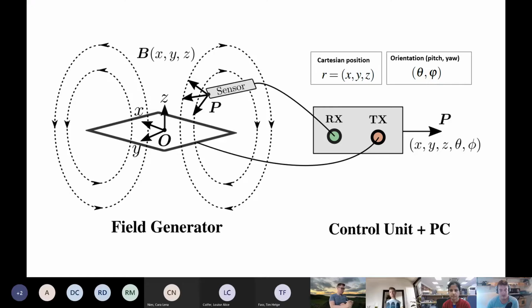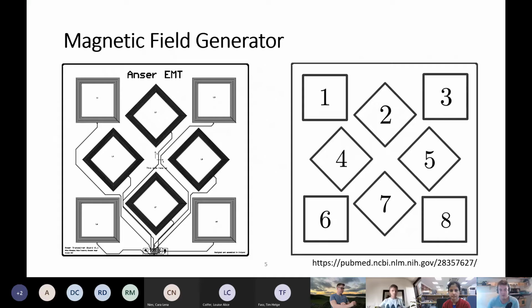The field generator is pretty cool—it's built from a printed circuit board with 8 discrete coils on it. Each coil transmits a low frequency magnetic signal in the kilohertz range, and each coil transmits a slightly different signal. For instance, the first coil might transmit 2 kilohertz and the 8th coil might transmit 10 kilohertz, and you can set them up to transmit any frequency you want. By having these different frequencies, you get a spatially unique magnetic field, meaning that for every point in space the magnetic field is unique. Based on that, when the sensor is at some position, you can measure that signal and find out the position.